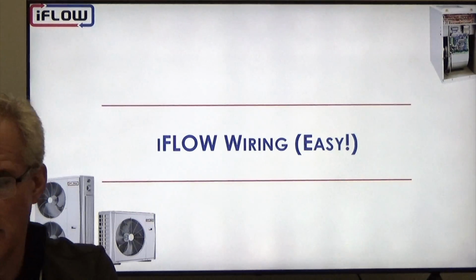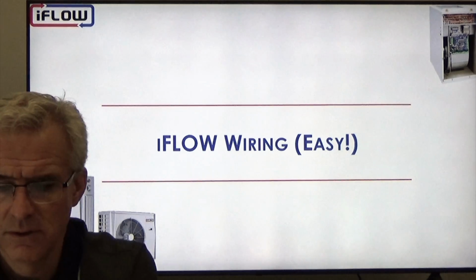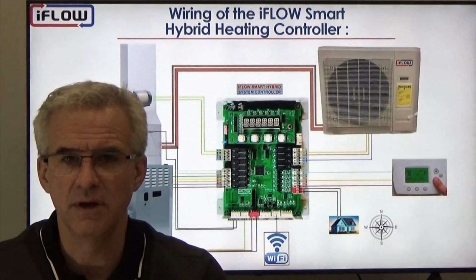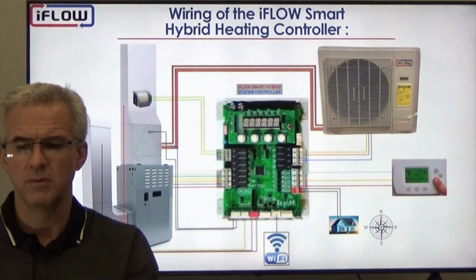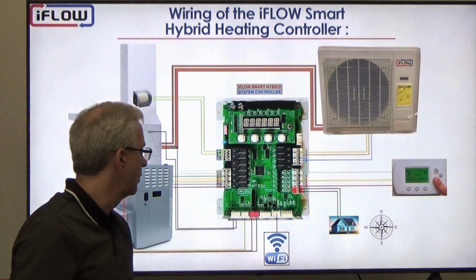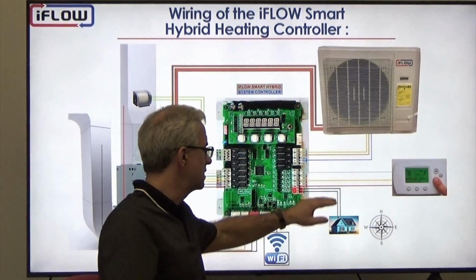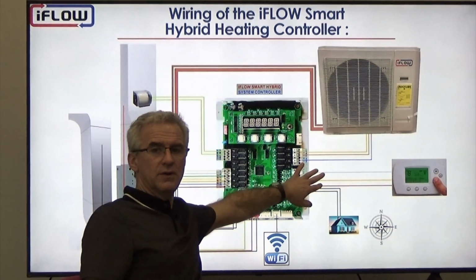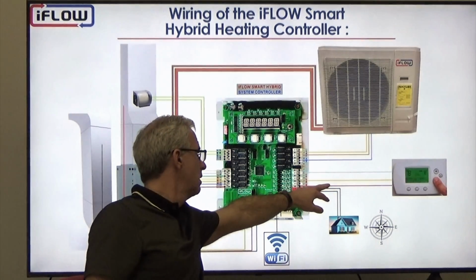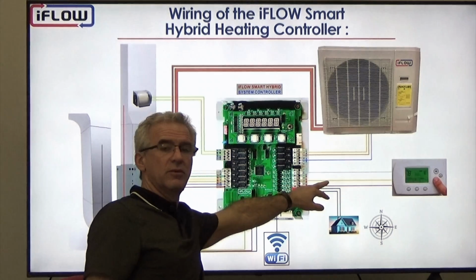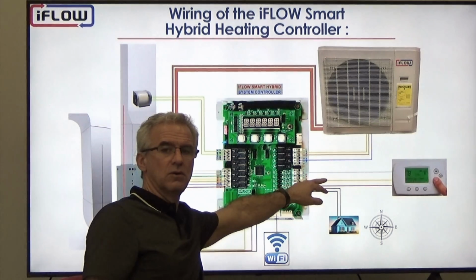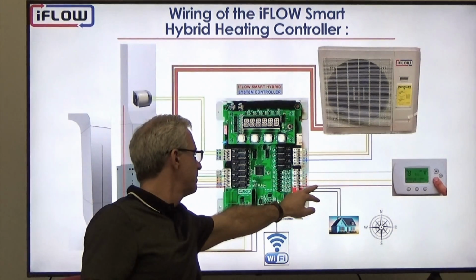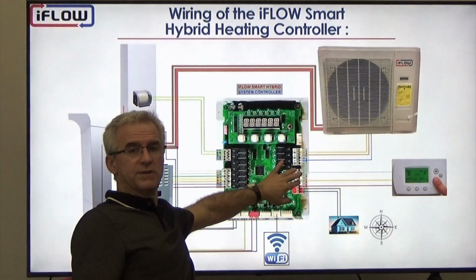So let's look at the wiring. The wiring to the iFLOW unit is fairly straightforward. As we mentioned earlier, we can operate with 3 wires. So in this example, we've just got 3 wires from the thermostat. We've got an R, we've got a W, and we've got a Y. So we've got a heating call, a cooling call, and then the power wire. So those are our inputs.